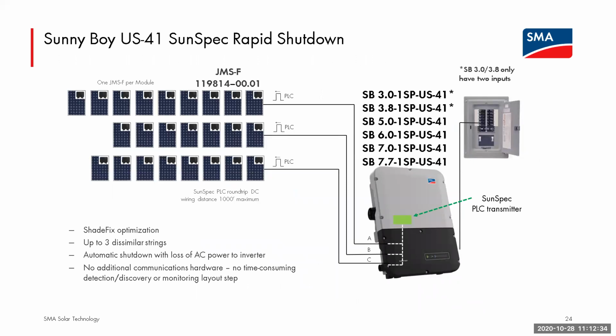So here's just another visual of that for our residential inverter, the Sunny Boy. We're showing here on the right the Sunny Boy power classes, the 3 MPPTs, the built-in SunSpec transmitter, and then, for example, 3 strings up on a roof, each solar module being equipped with our latest rapid shutdown unit called the JMS-F, 1 per module. So this is a real basic setup of what you would choose and what materials you would need to have a code compliant rooftop system with module level shutdown. That will give you NEC 2014, 2017, or NEC 2020 compliance.